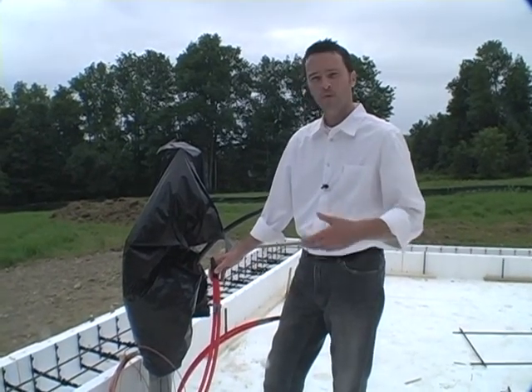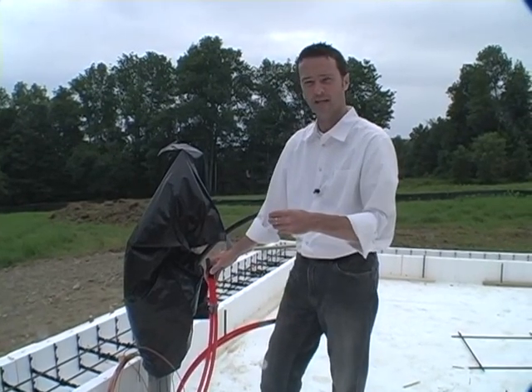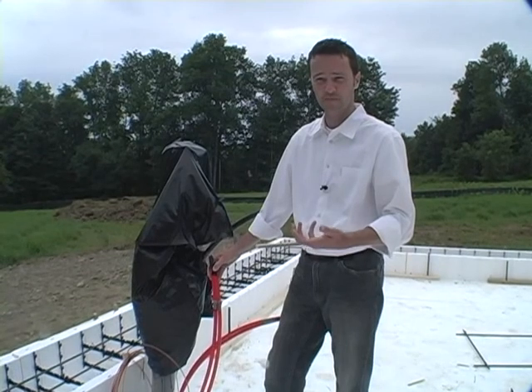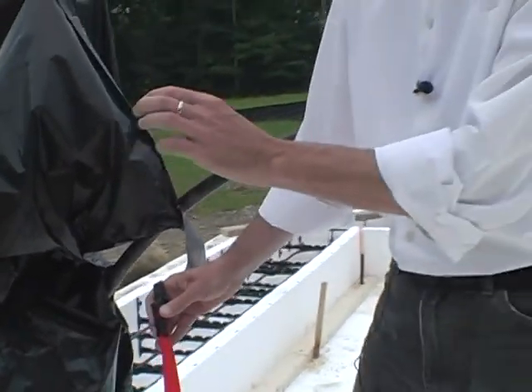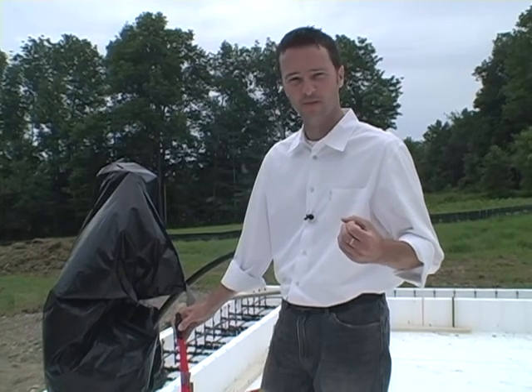When we build the house, we'll provide heat recovery ventilation for a healthy indoor air environment, and we'll use the Earth's heat to temper that incoming air from the exterior in the wintertime. In the wintertime, we can expect it to get down, as we all know, in Maine, to 0 degrees, and that incoming air can oftentimes freeze up the heat recovery ventilation unit. So using these tubes, we can use the Earth's heat to warm the incoming exterior air from 0 degrees to about 50 degrees. In doing that, we substantially increase the performance of the heat recovery ventilation, which in the long run has a strong effect on the overall energy performance of the building.